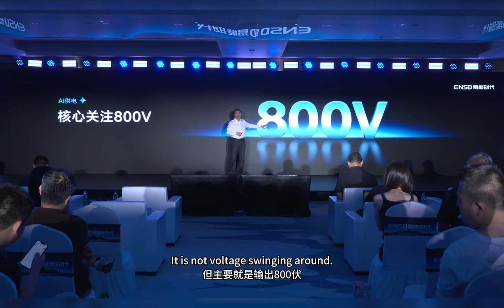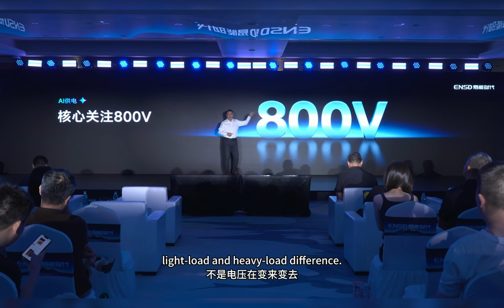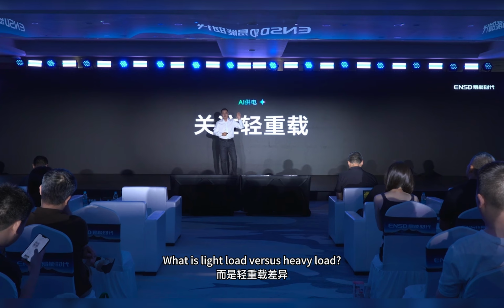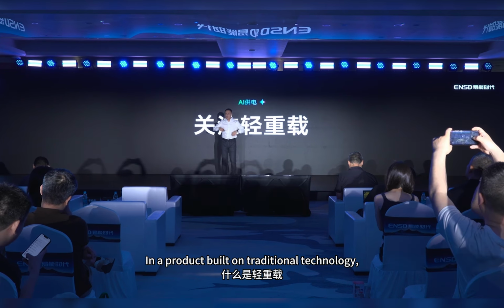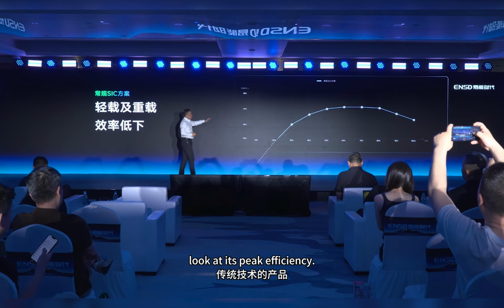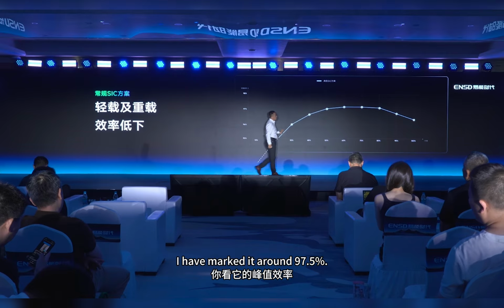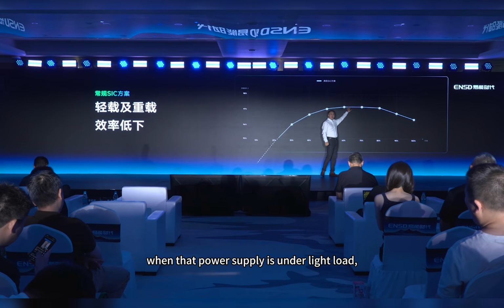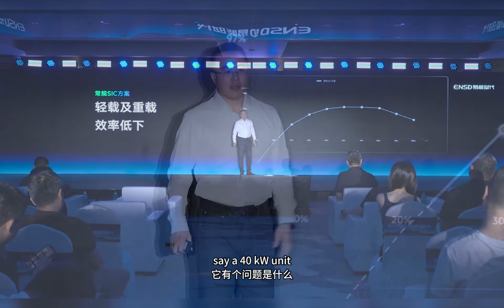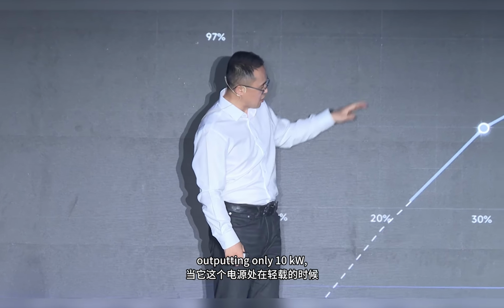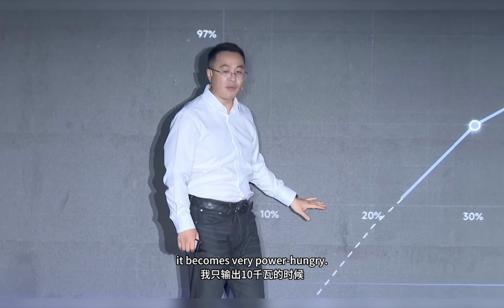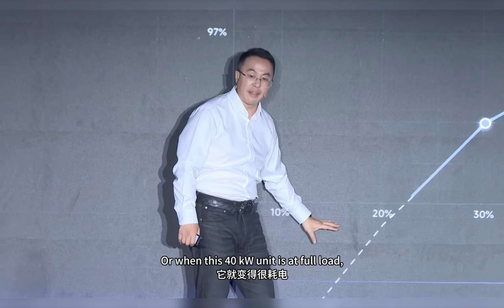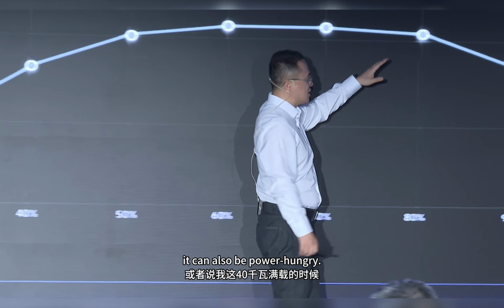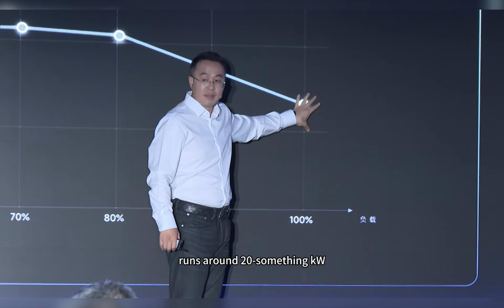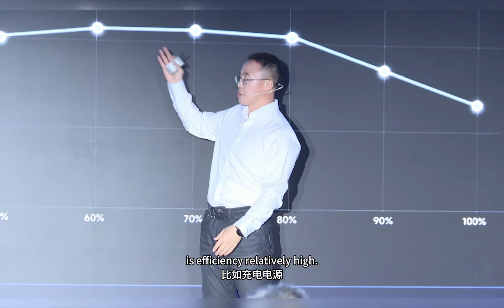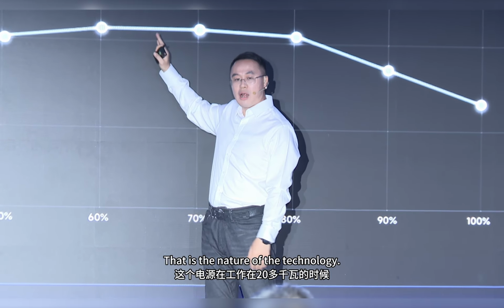It is not voltage swinging around, it is light load versus heavy load difference. What is light load versus heavy load in a product built on traditional technology? Look at its peak efficiency, marked around 97.5%. But the problem is this: when that power supply is under light load, say a 40 kilowatt unit outputting only 10 kilowatts, it becomes very power hungry. Or when this 40 kilowatt unit is at full load, it can also be power hungry. Only when this power supply runs around 20-something kW is efficiency relatively high. That is the nature of the technology.